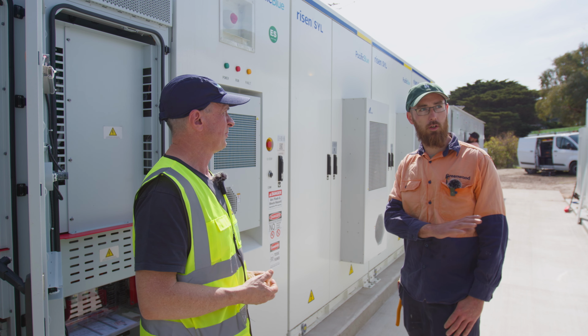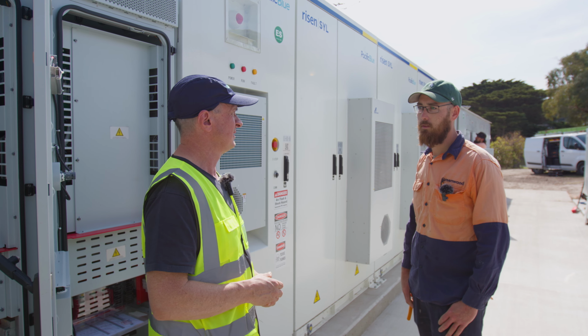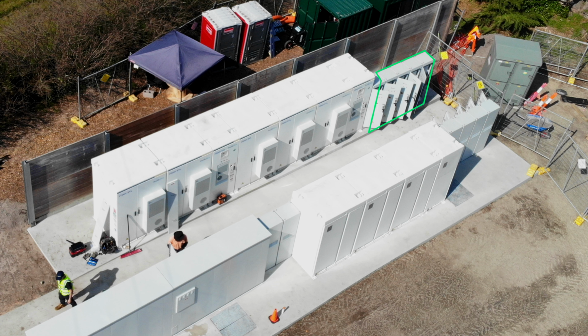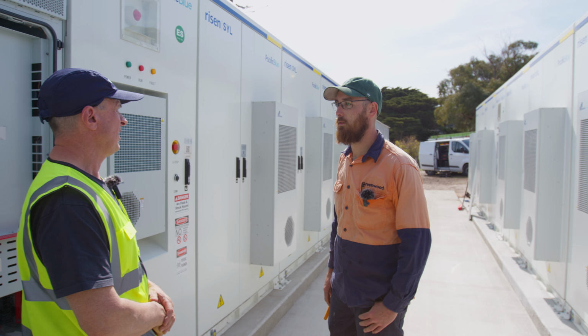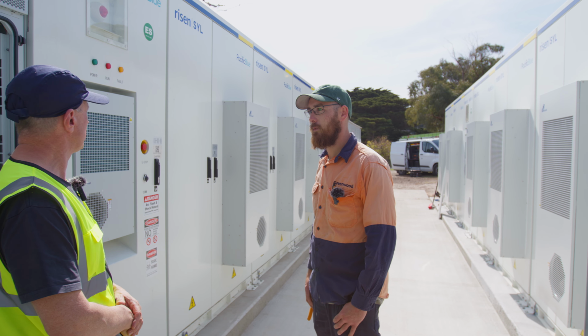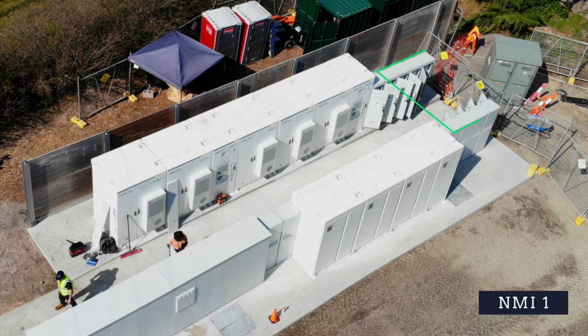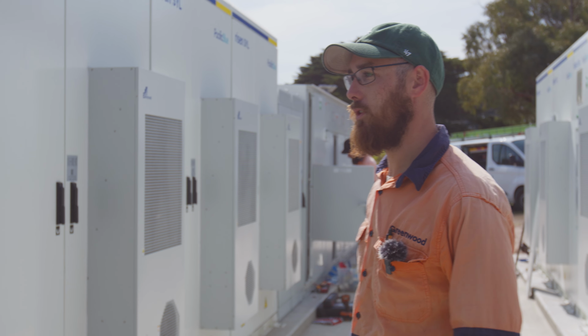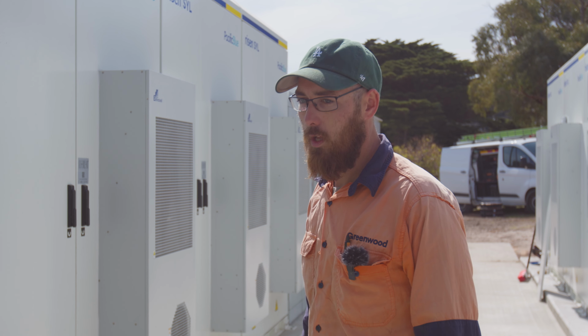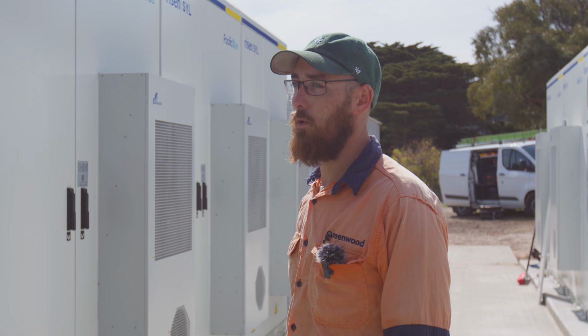As you can see, we've got 2 sides, which is actually 2 separate systems. So 5 inverters make up one system, and they're connected to 3 batteries. And these 5 are connected to another 3 batteries on this side. Okay, but all up, how many batteries are we talking about? I thought there was a few more than that. Well, this site, because of the 2 NMI situation, this is 1 NMI, has 10 inverters on it, whereas the other one has a further 2. So there's 12 inverters on site, which would bring this site to 1.2 megawatt of inverter power.